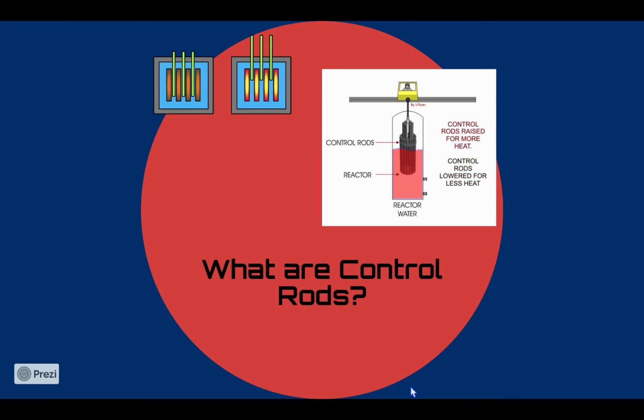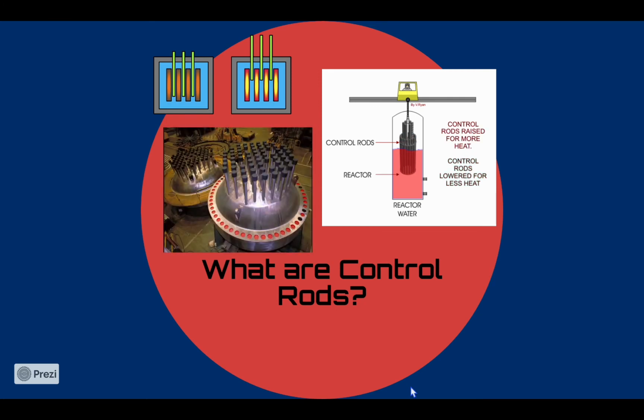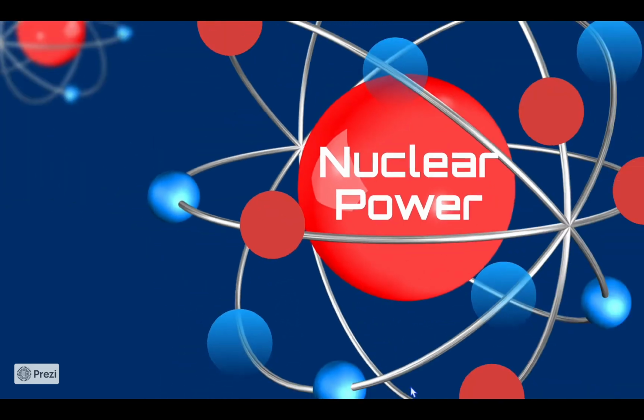However, it is important to note that there is a delayed response between the movement of the control rods and a reactor's fission rate. This is due to the presence of delayed neutrons released from the unstable nuclei that decay seconds or minutes after the original fission. These delayed neutrons induce further fissions, which ultimately delay the change in a reactor's fission rate.